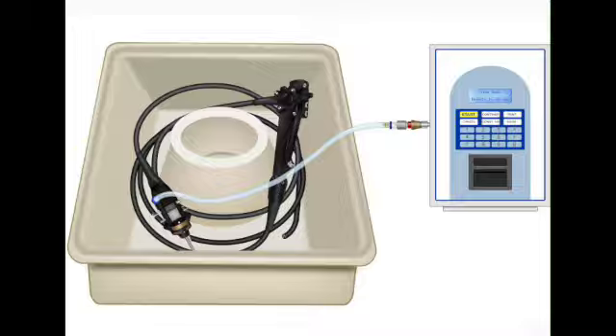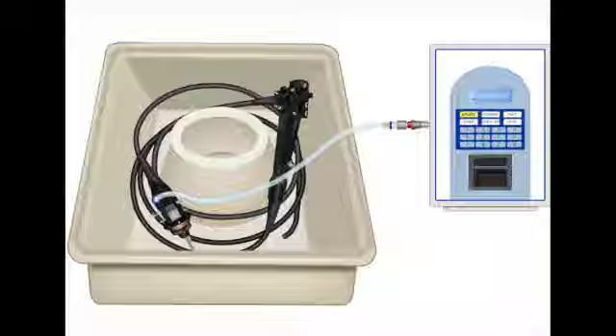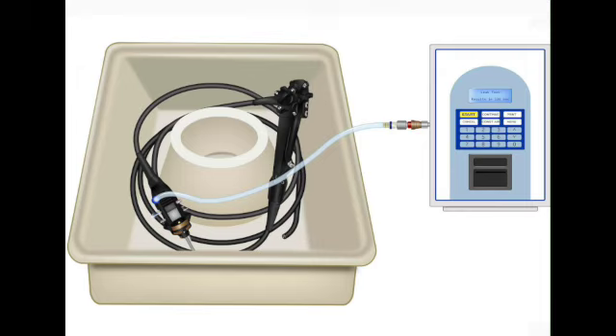The scope needs to be in a relatively relaxed position for an accurate test. Got it. Okay, so it's hooked up, it's positioned correctly, and you hit start on the machine. Now you can just grab a coffee? Definitely not. This is where the technician's job is so critical. It's not passive. While that machine is running and monitoring the pressure, you have to be actively working the scope. What do you mean by working it? You have to turn the knobs, flex the bending section all the way up, all the way down, right and left. You press all the buttons, image capture, freeze, you name it. And you're doing that to sort of simulate what it goes through in a procedure.